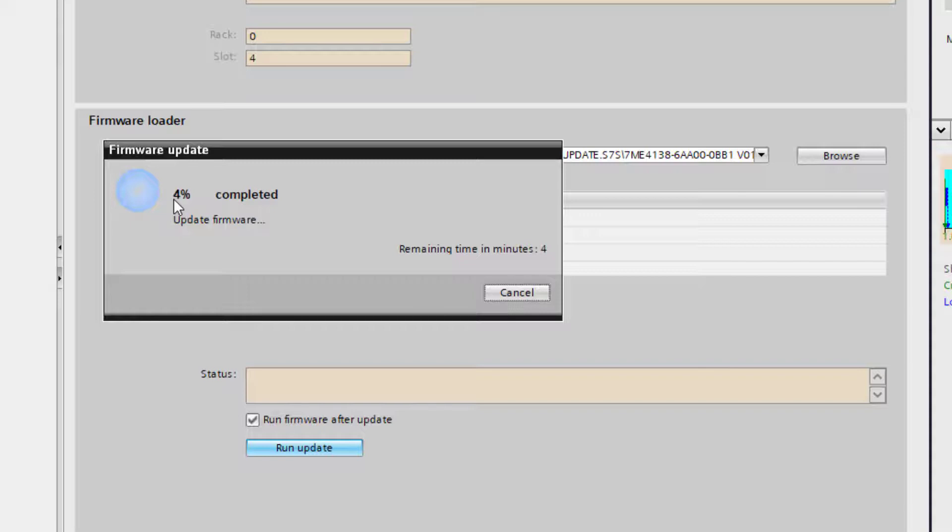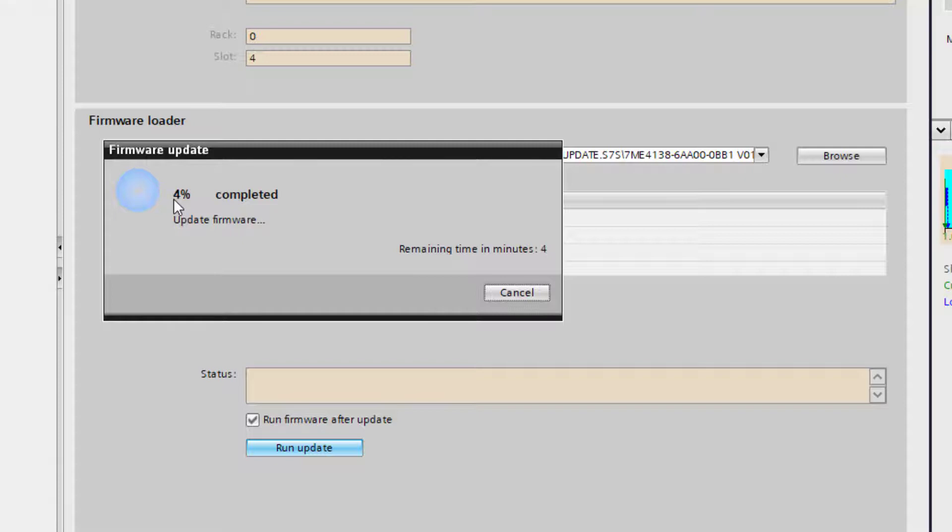I did try to upgrade this over WiFi to start off with and the upgrade time was 75 minutes but I had quite a few where I would lose comms and I'd have to start again. So my advice is to use a hard wired connection to your PLC or your IO rack and do the upgrade that way.